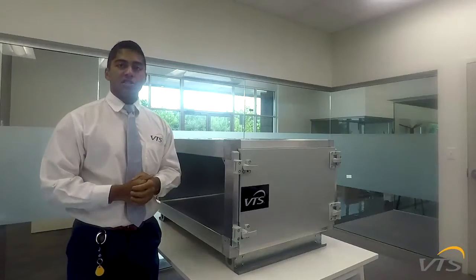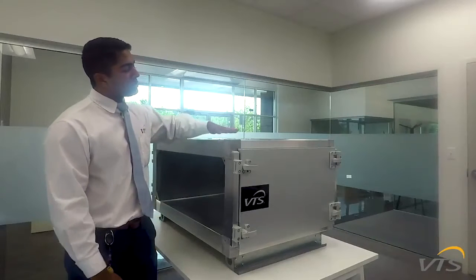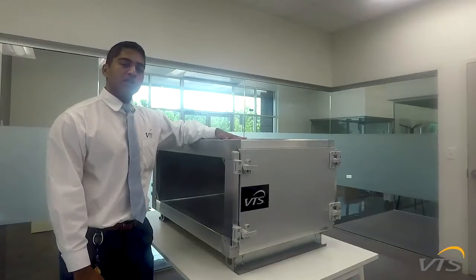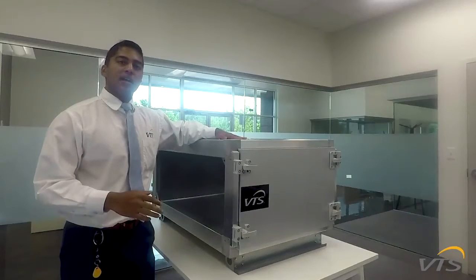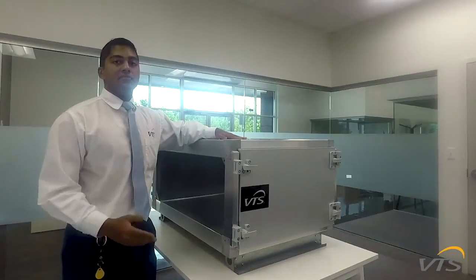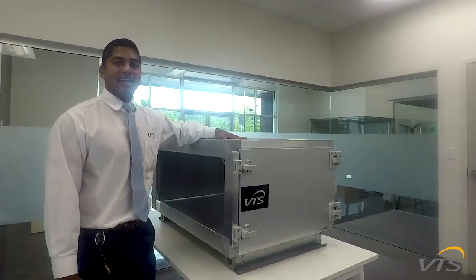This really adds to the rigidity. So on a performance basis, we achieve a deflection ratio of L/300 at plus or minus 10 inches of static, where you typically see an industry standard being either L/200 or sometimes a bit stiffer at L/240. And most of the time this is tested at only plus or minus 8 inches of static.